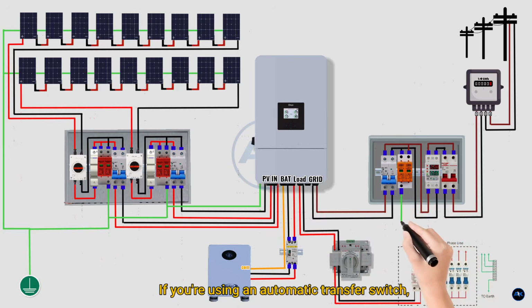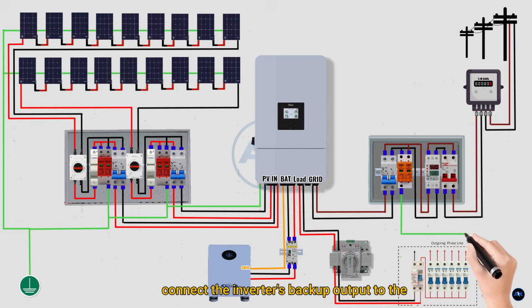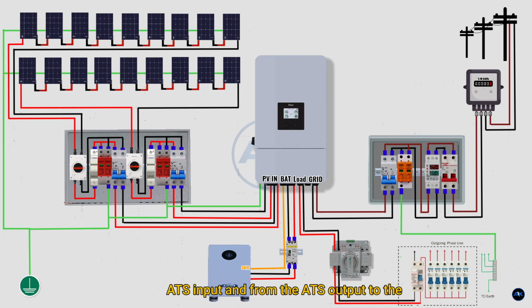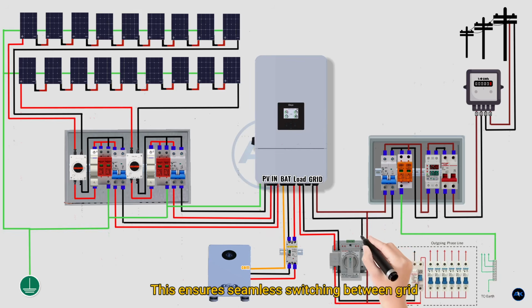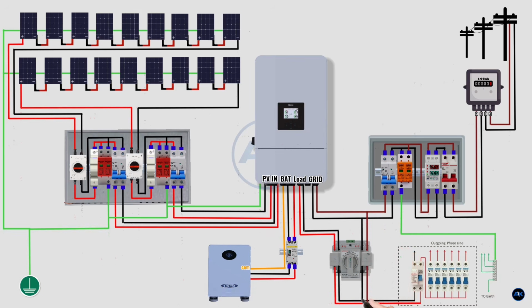If you're using an automatic transfer switch, connect the inverter's backup output to the ATS input, and from the ATS output to the essential loads panel. This ensures seamless switching between grid and inverter power without interruption.